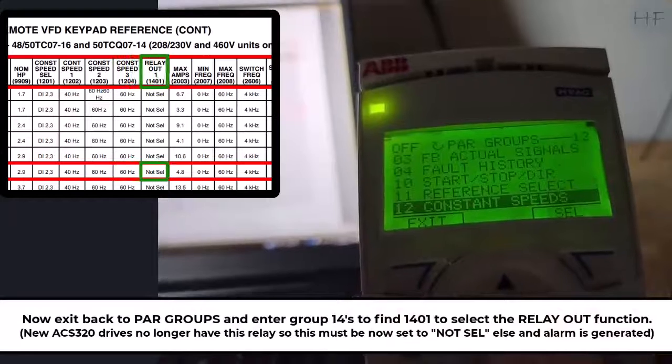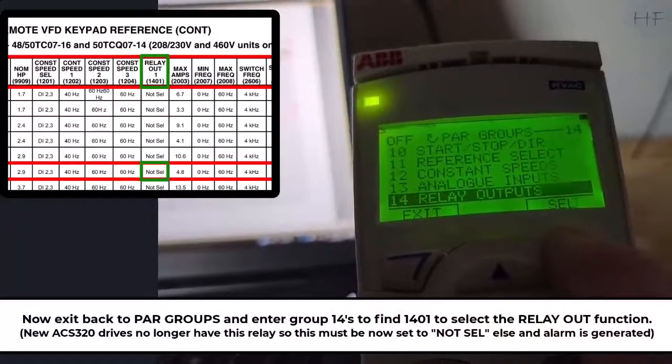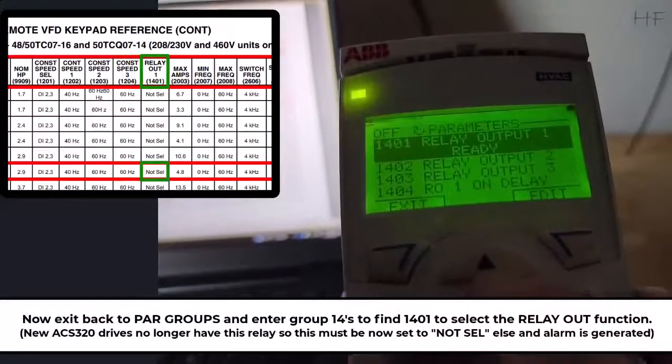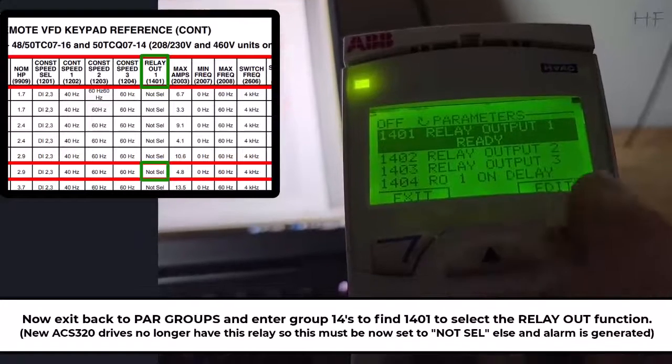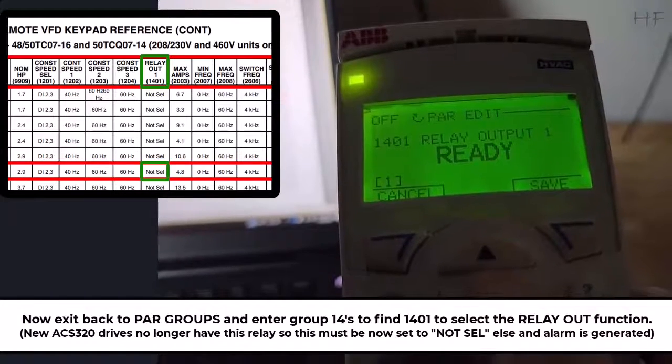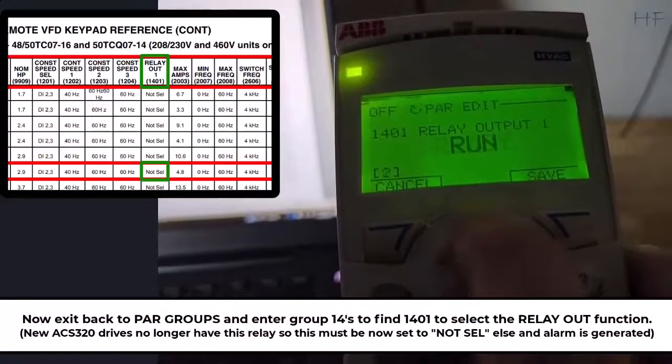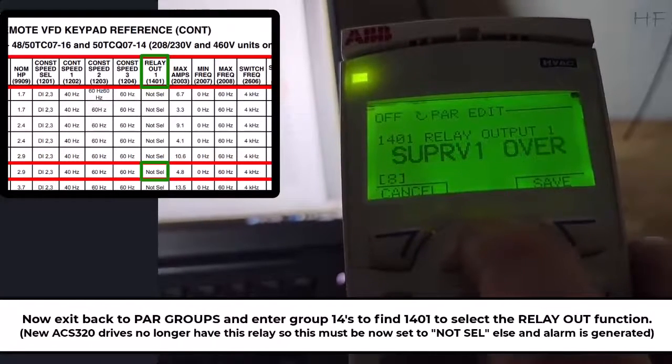Now exit back to parameter groups and enter group 14 to find parameter 1401 and select the relay output function. Note that newer ACS320 drives no longer have the relay so this must be set to not selected, else an alarm is generated.